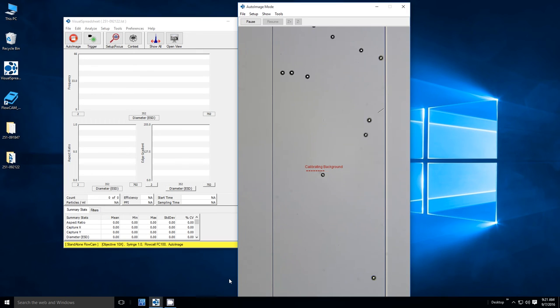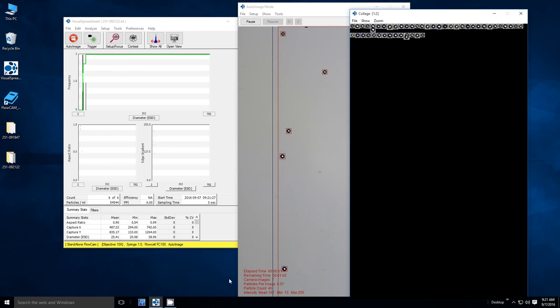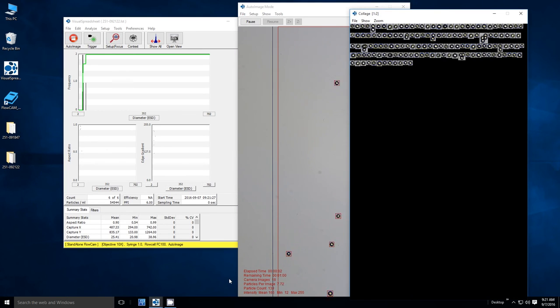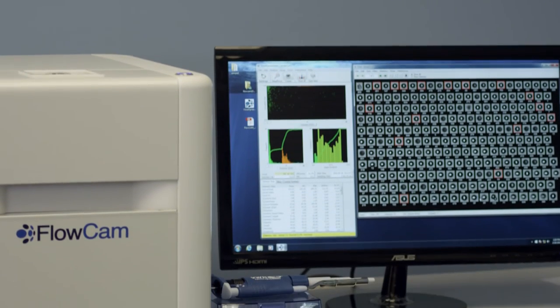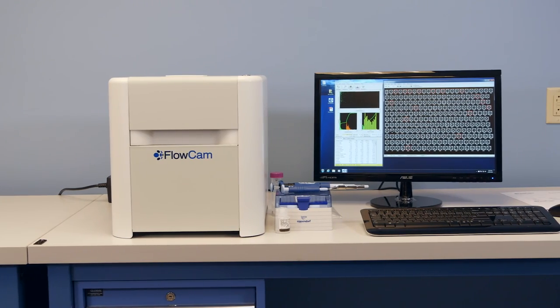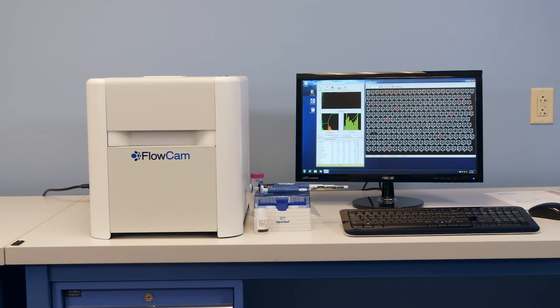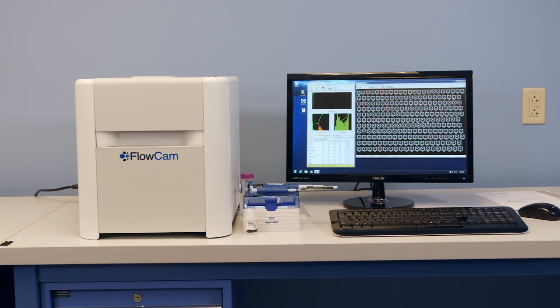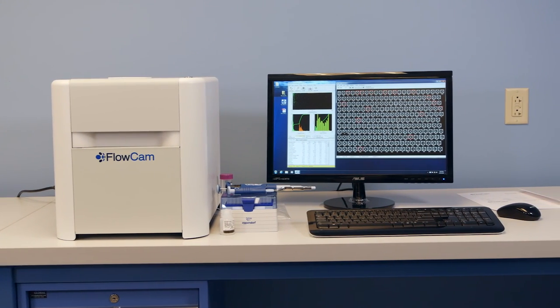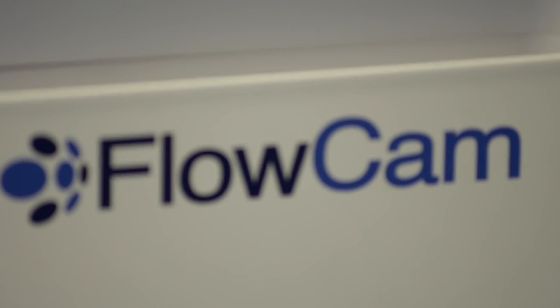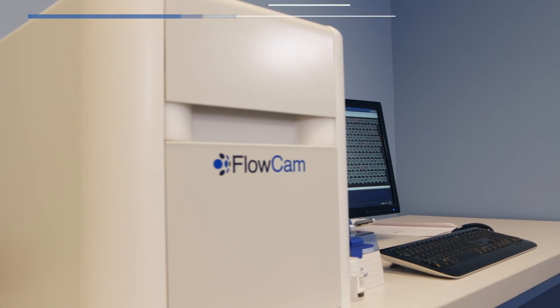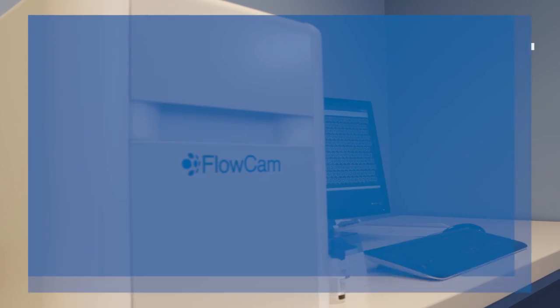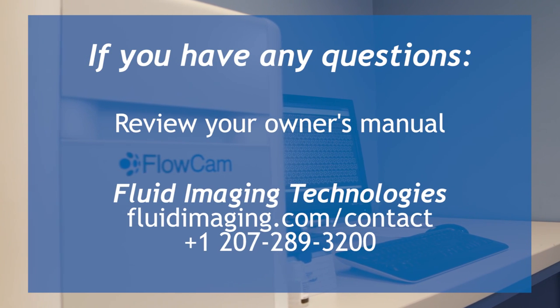The fluid position sensor will be able to detect the leading and trailing meniscus of the sample, thus determining when is the proper time to begin and end the analysis. You have now successfully set up and analyzed a sample with the FlowCam 8100. Please refer to our additional videos which cover other important topics within the Visual Spreadsheet software and for exporting data. If you have any further questions about operating your FlowCam 8100, please review your owner's manual or contact Fluid Imaging Technologies.